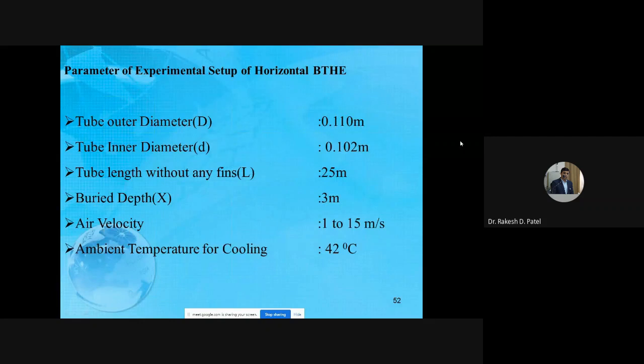Now, the parameters of the experimental setup of the heat exchanger. The tube outer diameter is 0.110 meter, the inner diameter is 0.102 meter, and the tube length without any fins is 25 meter. The buried depth is 3 meter. Air velocity varies from 1 to 15 meter per second, and the ambient temperature for cooling is 42 degrees centigrade. These are average data taken for designing the actual heat exchanger.